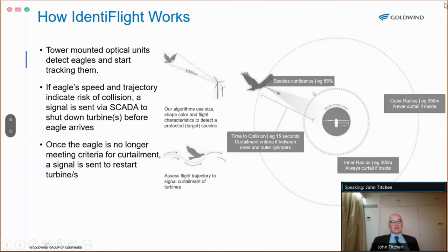So how the system works is these tower-mounted optical units detect the eagles and track them. If the eagle's speed and trajectory suggests a real risk of collision, not a miss, then a signal is sent to the SCADA to shut down the turbine before the eagle arrives. And once the eagle is outside that risk area, a signal is sent to start up the turbine again.